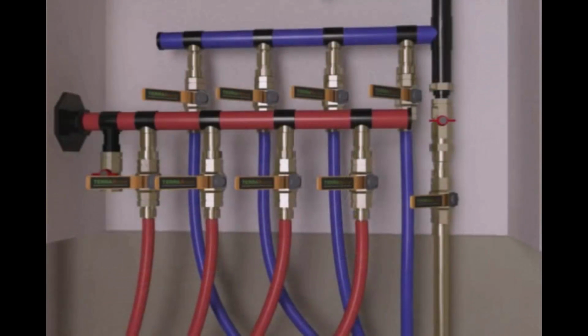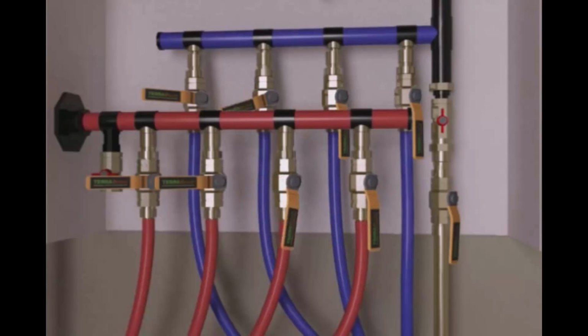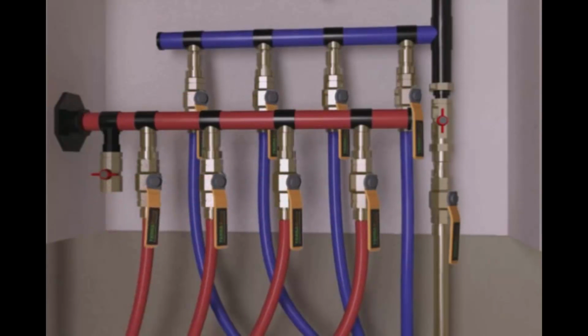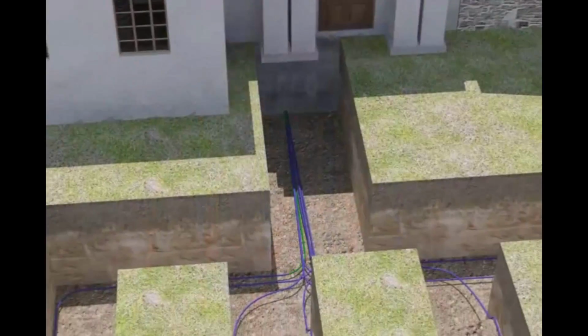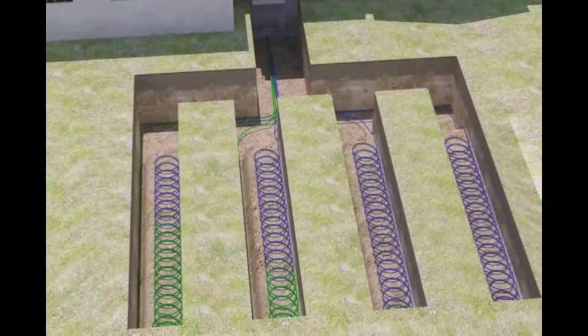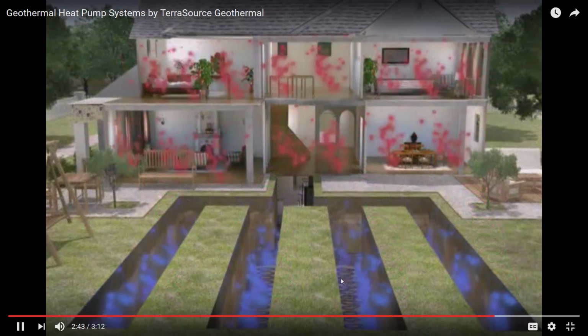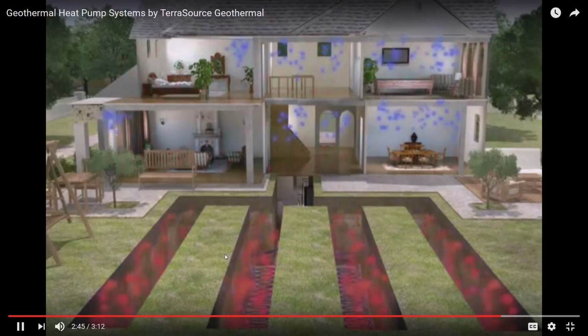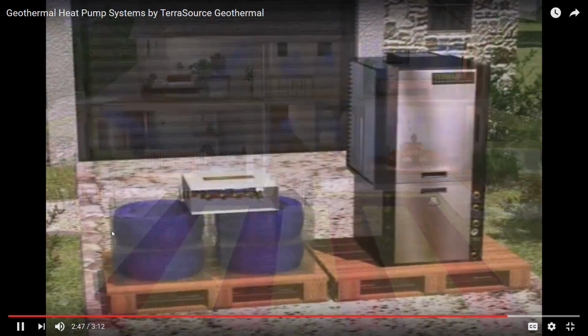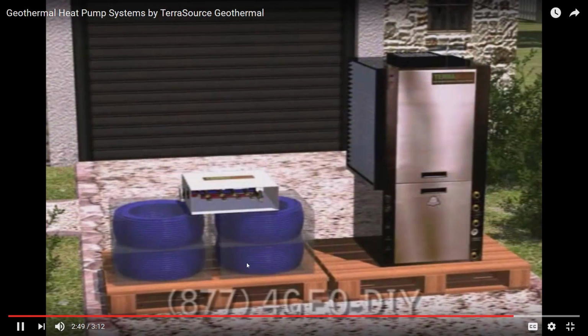To finish, fresh water is added. By using the port valve, each loop can be isolated and purged independently, thus eliminating the need for a flush cart. Antifreeze will mix throughout the loop field, while air is purged from the system. Your system is now up and running, and you will begin to realize some energy savings. The system can be installed by a TerraSource certified installer, or we can provide everything you need except for the digging and ductwork for a do-it-yourself install.